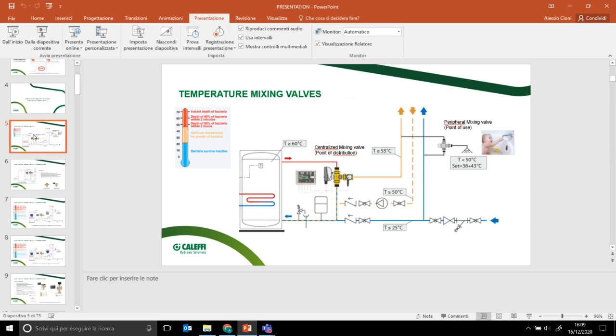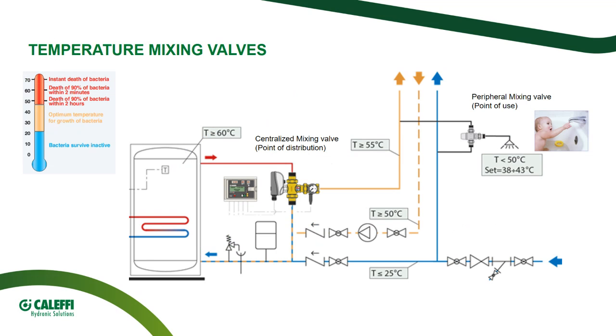Let's go to one of the first. Okay, for a matter of safety and for a matter of energy saving, basically. So let's suppose I have 60 degrees, but probably also 65 or 70, depending on the building. The heat loss of the system depends also on the temperature to which I distribute the water, and also the safety of the users, that can be also quite delicate, has to be always ensured. That's why this first temperature reduction. So if I distributed the water at 60, 70 Celsius, I might run into some issues throughout the season.